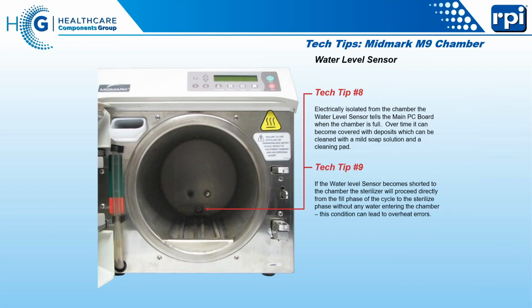Okay, water level sensor, we talked about that before, keep it clean. When you go to turn the machine on, if the machine immediately goes from fill to sterilize without waiting for the machine to fill, you've got a shorted water level sensor. The machine already thinks it's full of water. What's going to happen is it didn't put any water in at all, and in about 5 minutes, it's going to overheat. It's going to give you terrible errors. You're not going to build up any pressure. It's going to be terrible just because that water level sensor already thought there was water in the chamber.